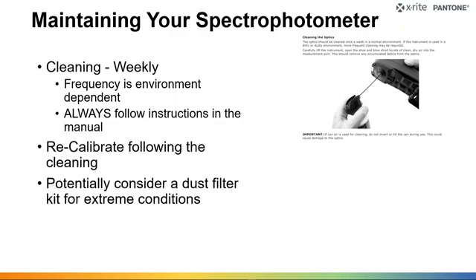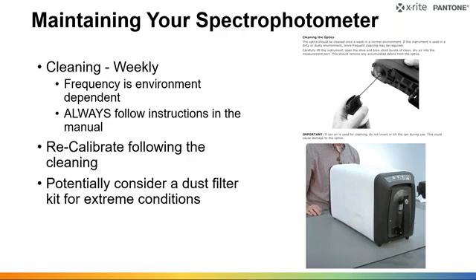And then for some extreme conditions, we actually have, for the benchtop device, a dust filter kit. And yes, that white is literally a filter. And so electronics, we all know that from looking at our computer monitors or our television sets or whatever, are magnets for dust, right? They create the electricity inside of them, turns them into electromagnets essentially, and dust just adheres to that. So if you're in a fairly dusty environment, it may mean that you need to be able to protect that device by putting that filter kit on there and stopping the dust from getting inside the instrument to begin with. Okay, so cleaning is very important.